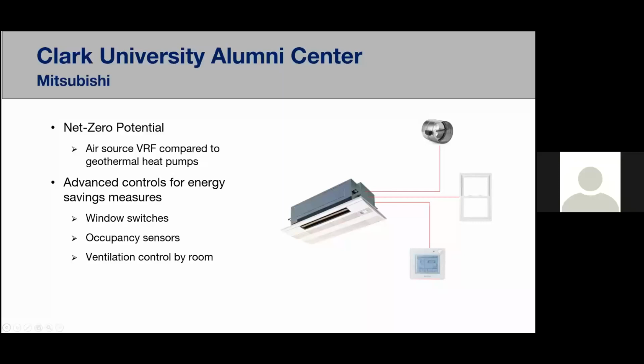And something that was cool about this project is we added some advanced controls for energy savings. So we added window switches. As soon as that window opened, it would shut off the ventilation and the fan coil unit. Occupancy sensors are located at one of these smart controllers right here. So if it wasn't occupied, then it would shut off your fan coil unit and your ventilation as well. And the ventilation was controlled by the room, by the local controller.